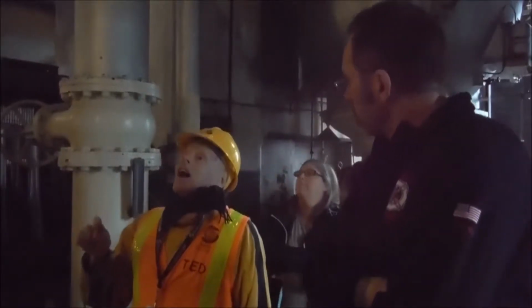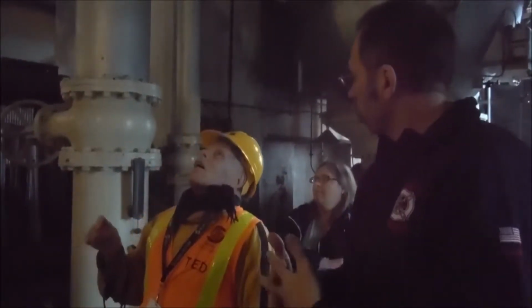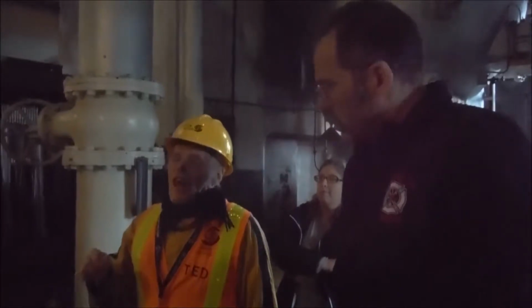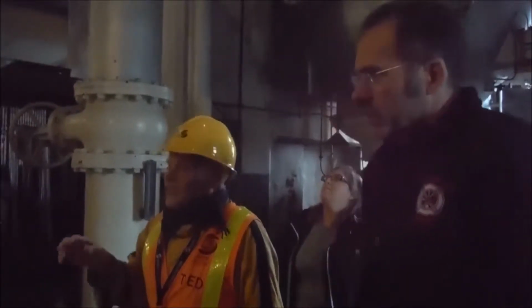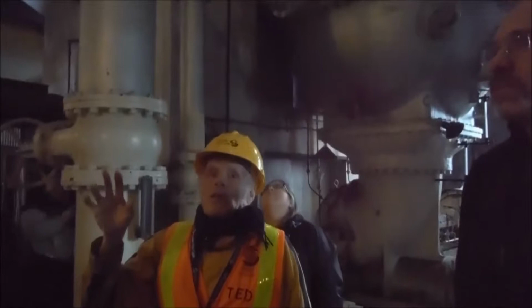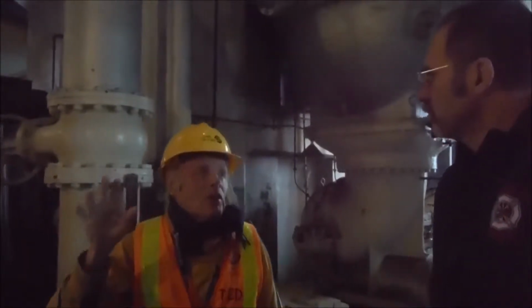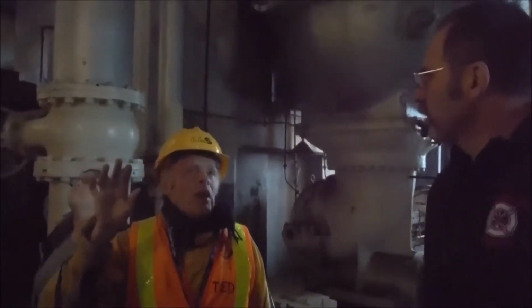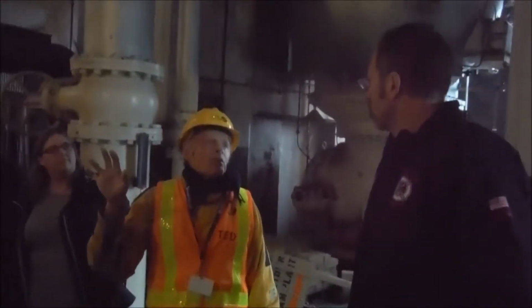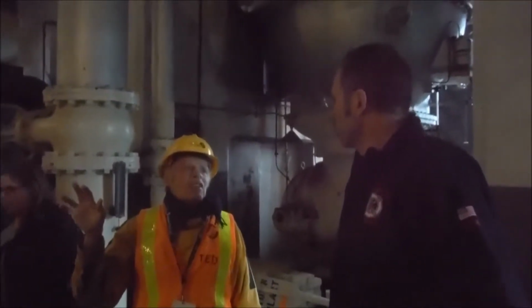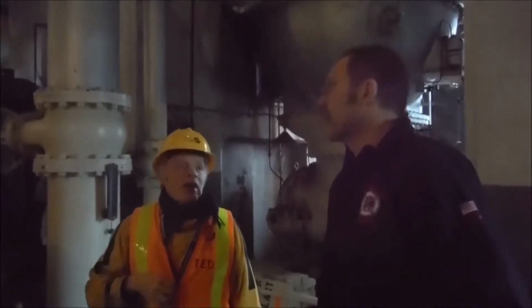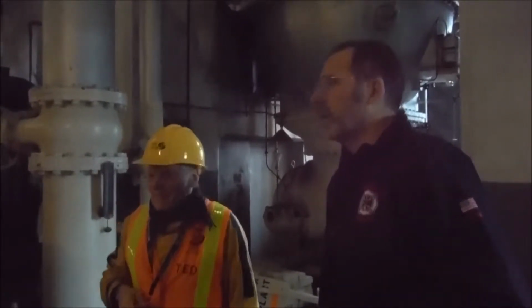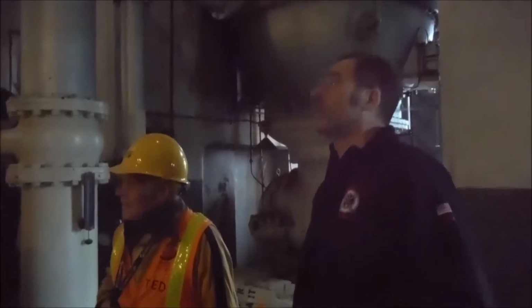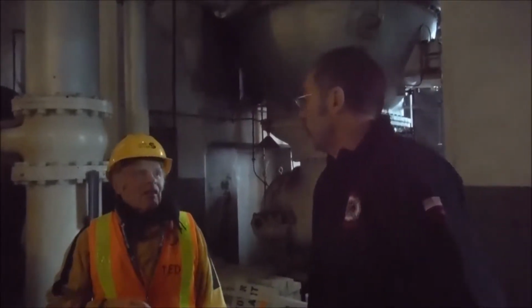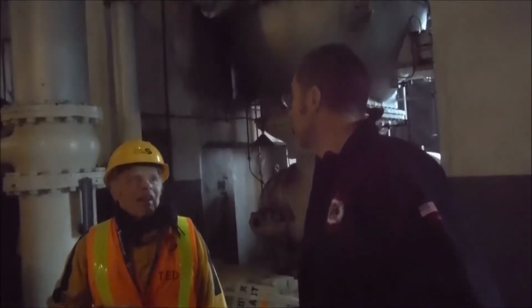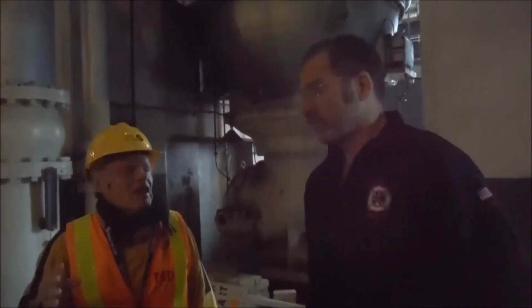So does the water mix? It kind of does, yes. And like I said, you have a vacuum pump because there's entrained air in the river water, and once you get the air out, you raise the vacuum from about 26 to 28 inches, giving very efficient operation. The lower the pressure in the condenser, the more efficient the steam turbine is, because you get more of the energy back out of the steam, since you're not pushing against atmospheric pressure.